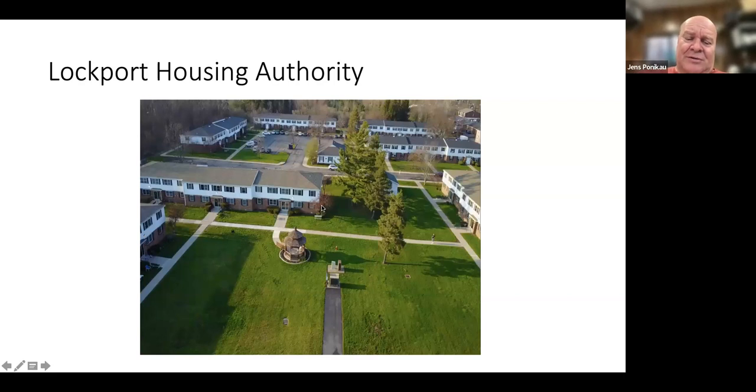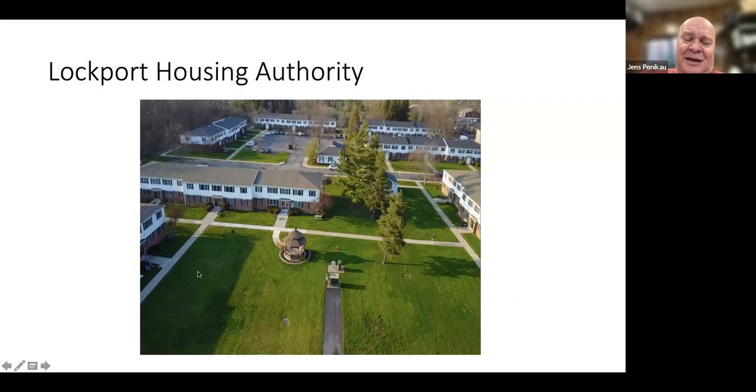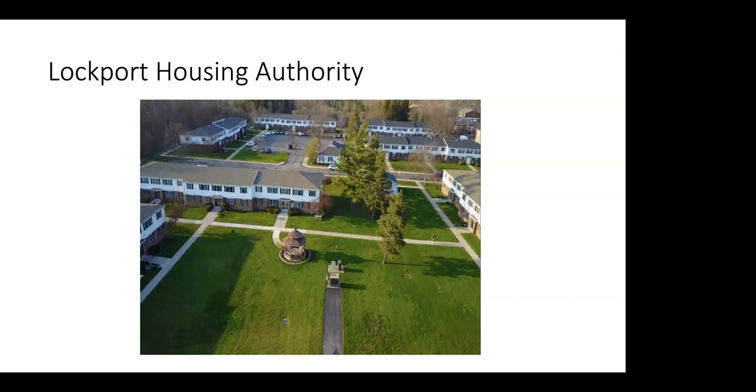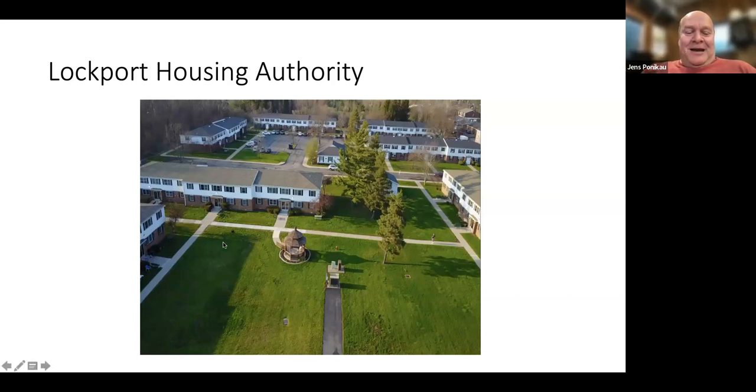We put the geothermal system in, making 100% of the domestic hot water and providing all the heating and cooling. And it's interesting, you see, this is the transformer for the entire development, and all the buildings are on one meter. So we have a not very granular, but very good picture: we know how much energy this was using before geothermal, and we know how much energy it is using after. This example is simply delivering one answer. You put in a geo system, and how much does it take down the energy use, in a larger multifamily? And by the way, it was electric heat before for both domestic hot water as well as heating and cooling.